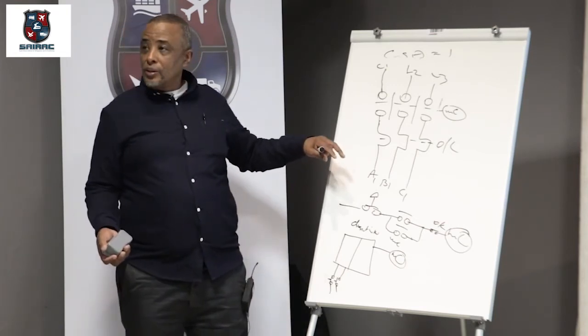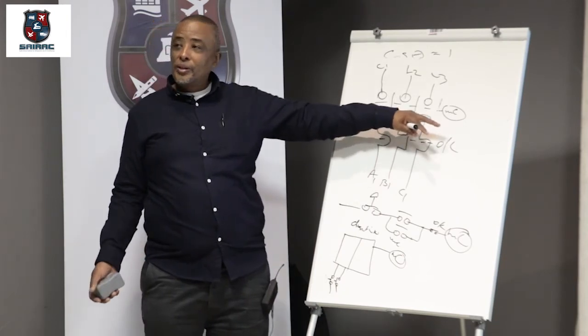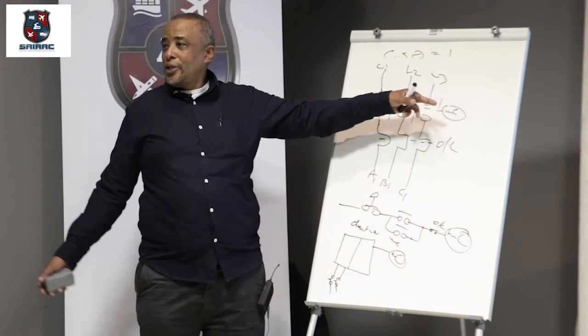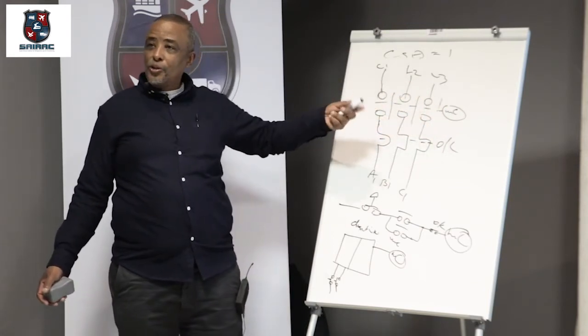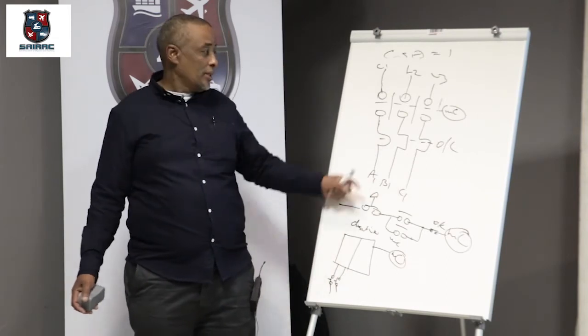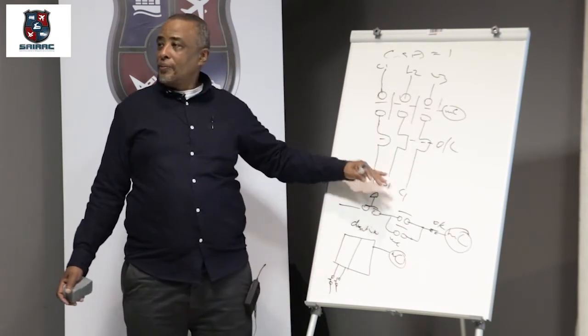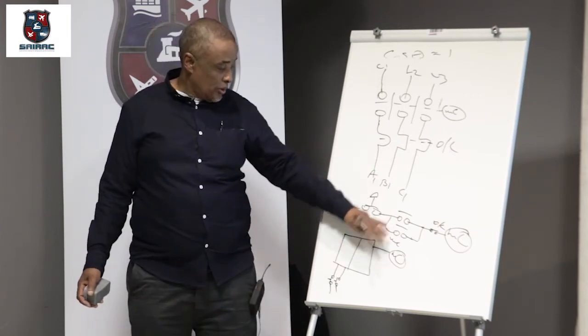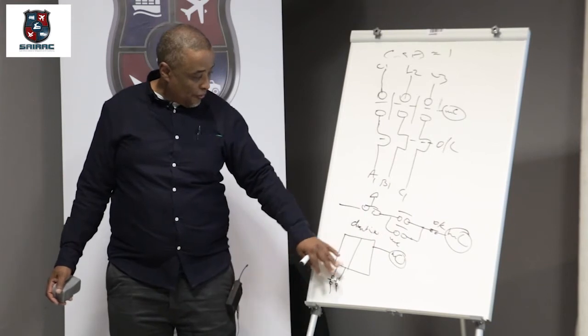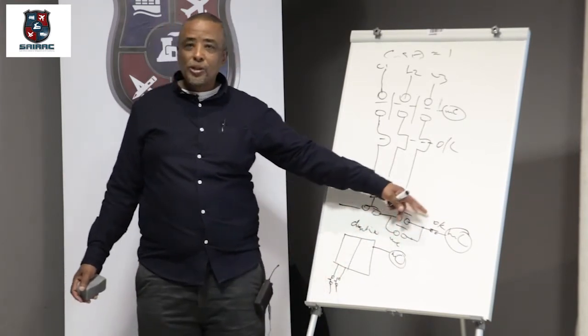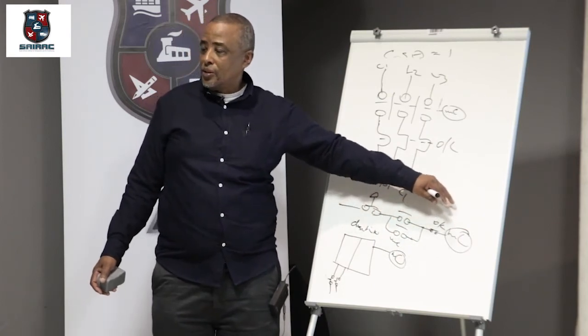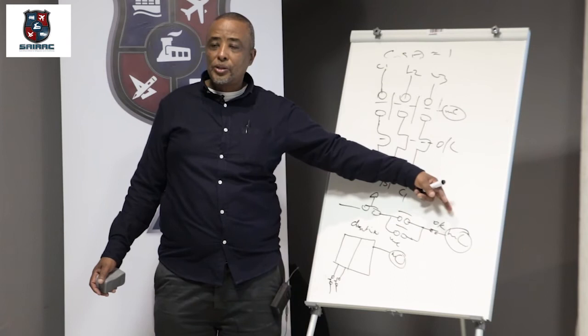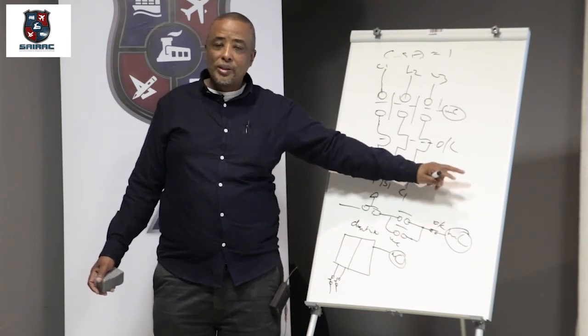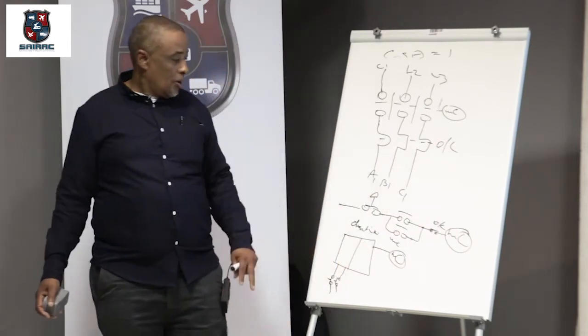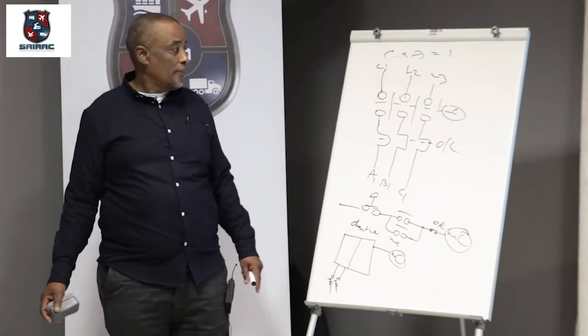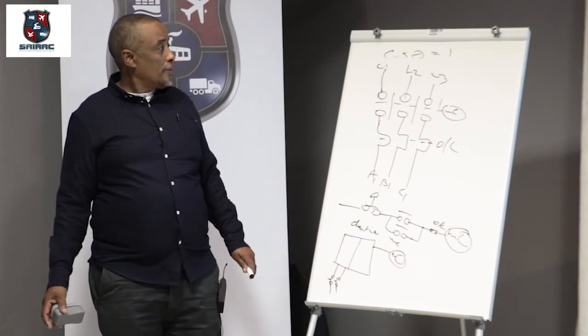Suddenly the power comes back on. Imagine if there was no under voltage protection. The guy was under the bandsaw, some machine, and could get hurt. So that machine will not start up automatically until you physically press the start button, energize that coil, the contactor comes in, and the motor runs. That could be controlled with a control circuit like that. You could add a whole lot of other safeties, proximity switches, whatever else you want to add. What you can add on the control circuit is endless. Or guys use mainly PLC today.